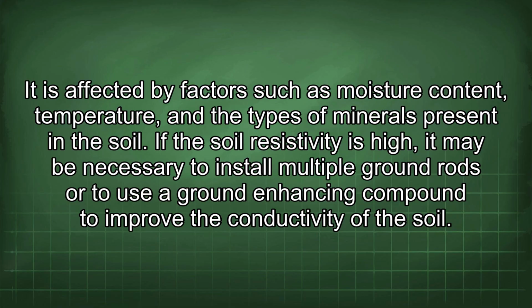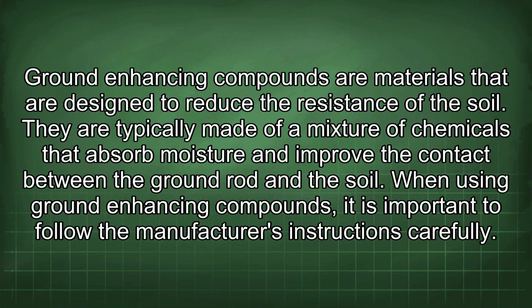If the soil resistivity is high, it may be necessary to install multiple ground rods or to use a ground-enhancing compound to improve the conductivity of the soil. Ground-enhancing compounds are materials that are designed to reduce the resistance of the soil. They are typically made of a mixture of chemicals that absorb moisture and improve the contact between the ground rod and the soil. When using ground-enhancing compounds, it is important to follow the manufacturer's instructions carefully.